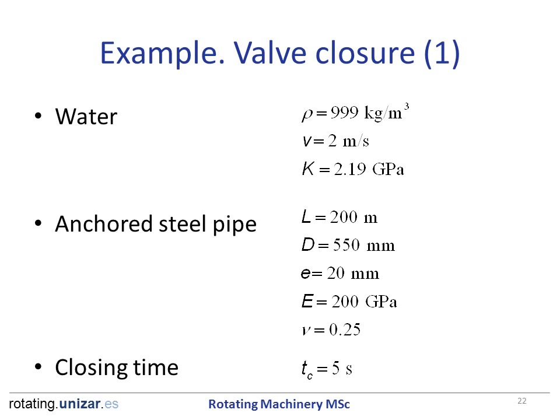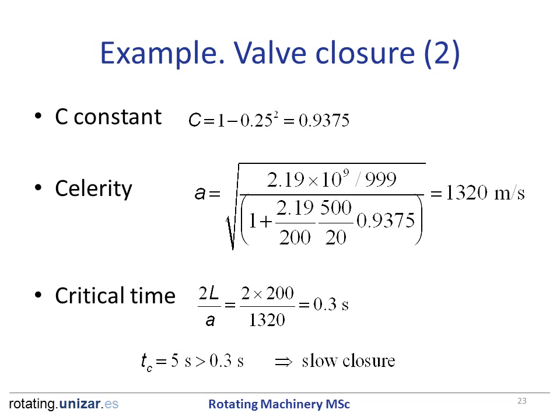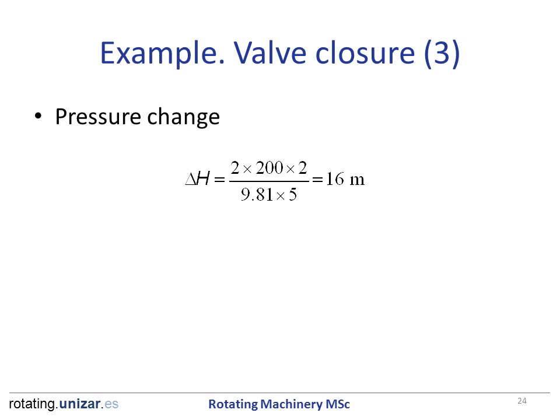This is an example of calculating the water hammer induced by a valve closure. Inside a pipe, we have water traveling at 2 meters per second. The pipe is an anchored steel pipe of 200 meters length. The closing time is 5 seconds. First, we compute the constant C for an anchored elastic pipe. Then we calculate the celerity and the critical time, which must be compared with the closing time. Since the closing time is larger than the critical time, the closure is slow. Therefore, the increase of pressure is given by Michaud's expression, resulting in 16 meters of column of water.